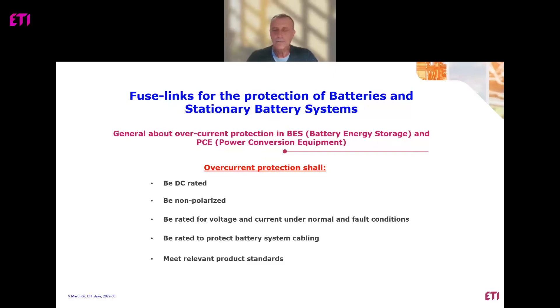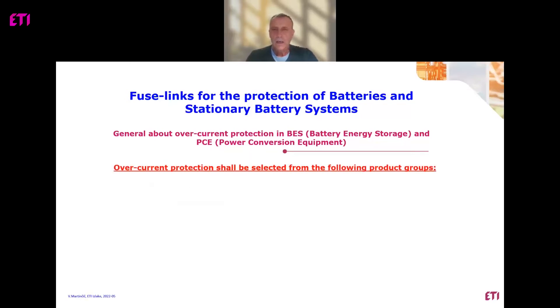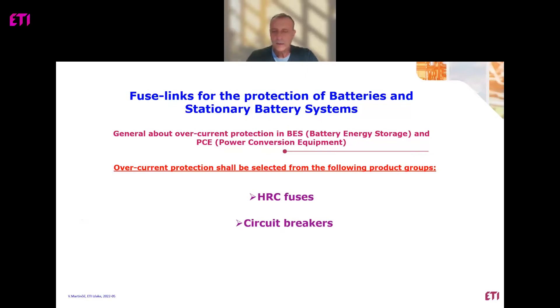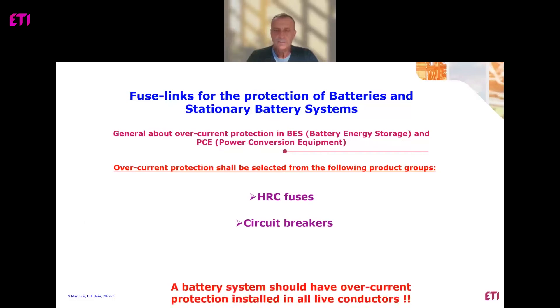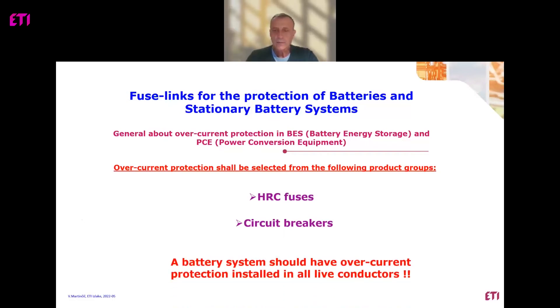Up to two years ago there was no proper standard for overcurrent protection. That is why overcurrent protection was selected from the following product groups: one is definitely high rupturing capacity fuses, second are circuit breakers and powerful MCCBs. Most importantly, the battery system should have overcurrent protection installed in all live conductors — this is very important and we should not forget it.